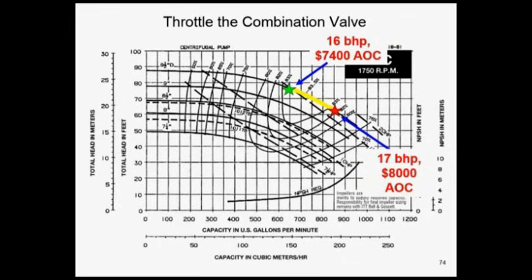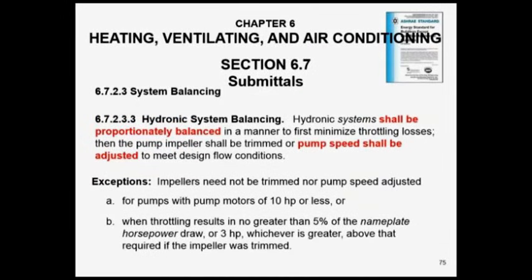We broke the law. We didn't meet ASHRAE 90.1 2010. Why did we not meet ASHRAE 90.1? Let's go back to balance. Go back to our hydronic balance statement here. Hydronic systems should be proportionally balanced in a manner to first minimize throttling losses, then pump impeller shall be trimmed, or the pump speed shall be adjusted to meet design flow.